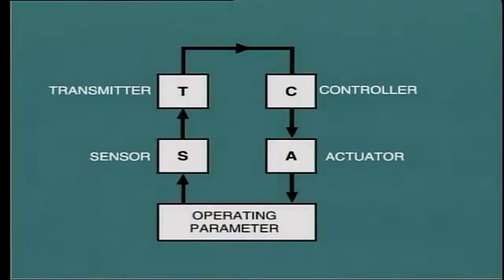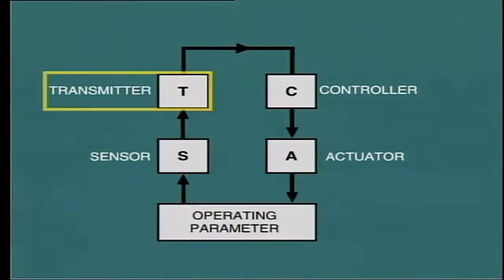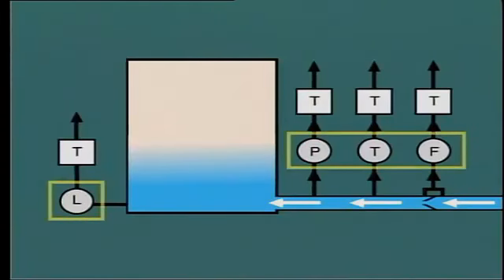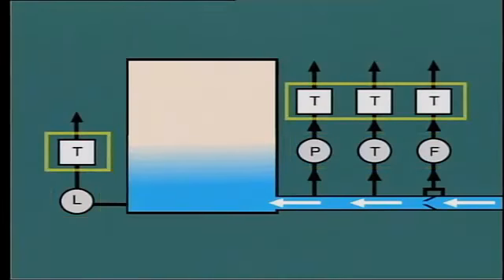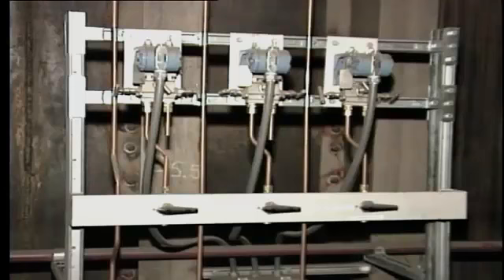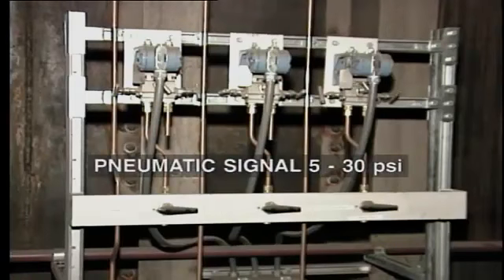This schematic shows the essential components of a control loop: the sensor, transmitter, controller, and actuator. The sensor measures the operating parameter being controlled, such as pressure, temperature, flow, or level. This information is then fed into the transmitter, which prepares the signal for transfer to the controller. Older installations still use compressed air as the signal medium, with pneumatic signal pressure typically varying between 5 and 30 psi depending upon the value to be transmitted.